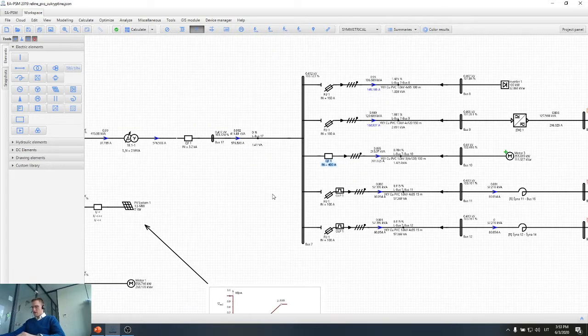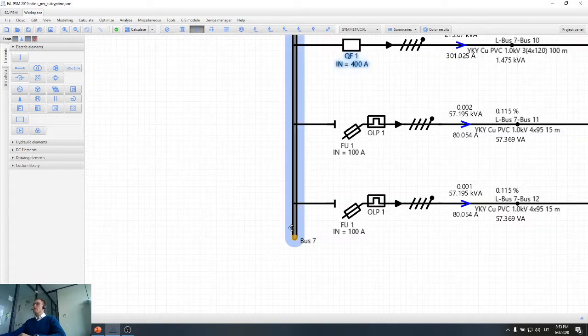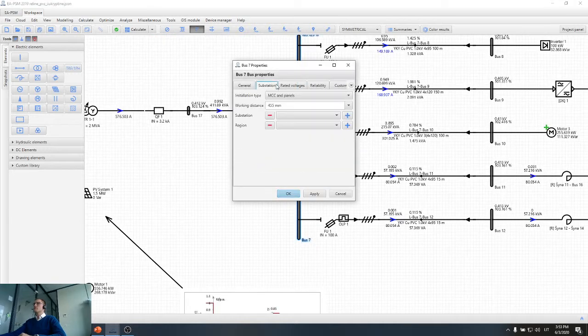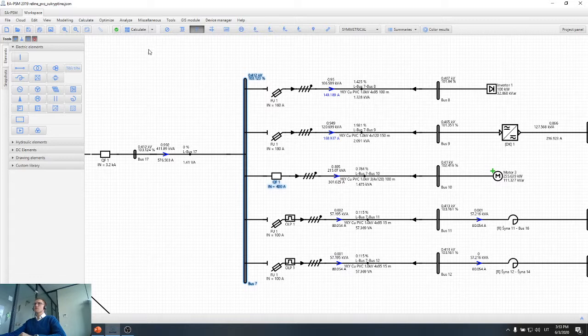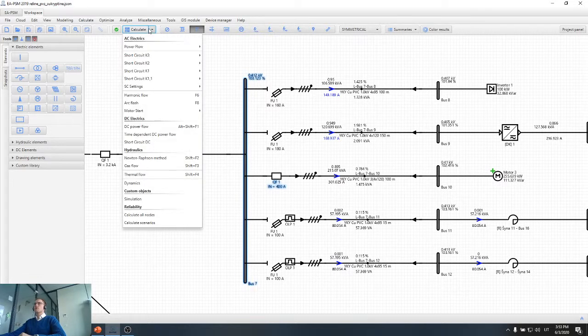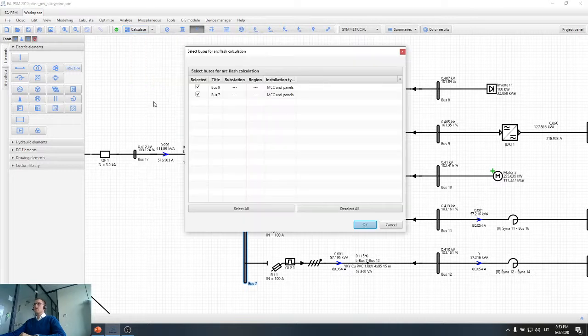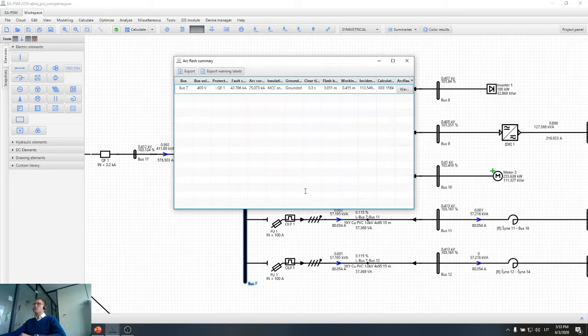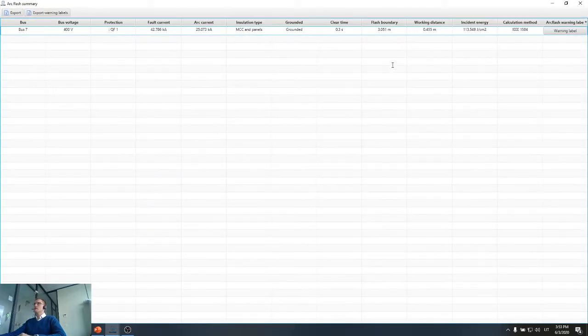So what we can do next in this kind of network, actually, we can also check arc flash conditions to make sure that arc flash is within the permissible limits. So let's try to calculate arc flash in bus 7. I will double click on the bus bar. Installation type for this bus bar is MCC and panels, so it's a motor control center or panel. Let's assume that this is a panel for our loads, and let's calculate arc flash in bus 7. The software will estimate the short circuit current and also the disconnection time for the short circuit in bus 7, and will estimate incident energy at working distance as well as the possible flash boundary.